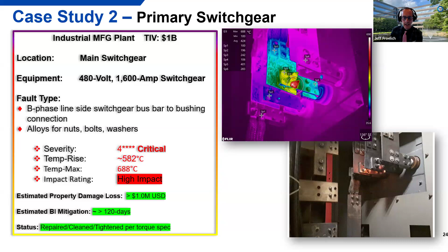In this case, this is probably one of the highest I've seen in my career, significant at a maximum temp of 688 degrees C. That's over 1200 degrees Fahrenheit. So you're at imminent failure. I'm surprised this thing hasn't already, but it just goes to show you. This went into emergency shutdown, and they were able to correct and repair it. It's probably one of those where you can't open it due to production cycles and other factors, but certainly advanced planning and taking it down before an unplanned outage was key. Next slide. Let's do one more.